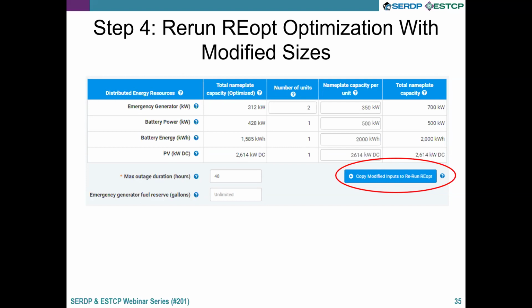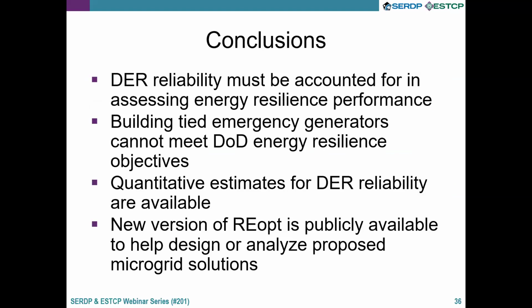On slide 36, to conclude: DER reliability is a fact that gets ignored far too often, but it must be accounted for in assessing energy resilience performance if we're really concerned about supporting critical loads. Building-tied emergency generators cannot meet DoD energy resilience objectives, even though they've been used for decades to do that. There's a total disconnect between their performance, even if well maintained, and the requirement for 2 weeks of energy resilience. We have quantitative estimates for reliability of DERs that don't require modeling—they're just based on empirical data.